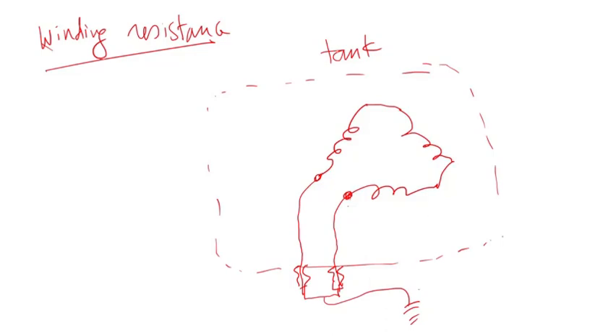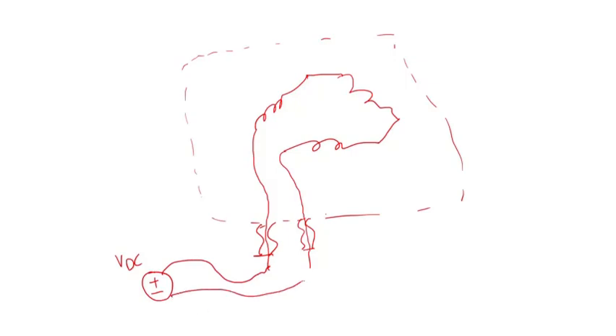Now to perform the winding resistance test, you have to remove this jumper here to ground. And also you have to remove this jumper that jumpers the bushing. So basically what you end up having is something like this. These 2 are jumpered together. Then you have the bushing. Then what you do, you apply DC voltage. As the DC source, you connect one side here, the other side. When you apply DC voltage, the circuit is complete, so current will flow. It's going to go through this winding, then through this winding, then through this winding, through this bushing, and back to the source. So there's a complete circuit.